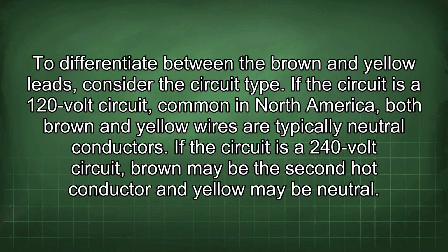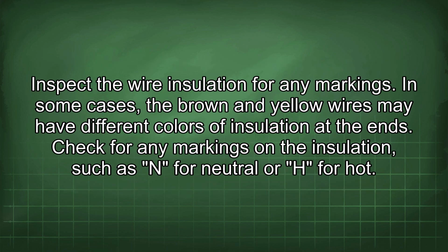To differentiate between the brown and yellow leads, consider the circuit type. If the circuit is a 120-volt circuit common in North America, both brown and yellow wires are typically neutral conductors. If the circuit is a 240-volt circuit, brown may be the second hot conductor and yellow may be neutral. Inspect the wire insulation for any markings. In some cases, the brown and yellow wires may have different colors of insulation at the ends. Check for any markings on the insulation, such as N for neutral or H for hot.